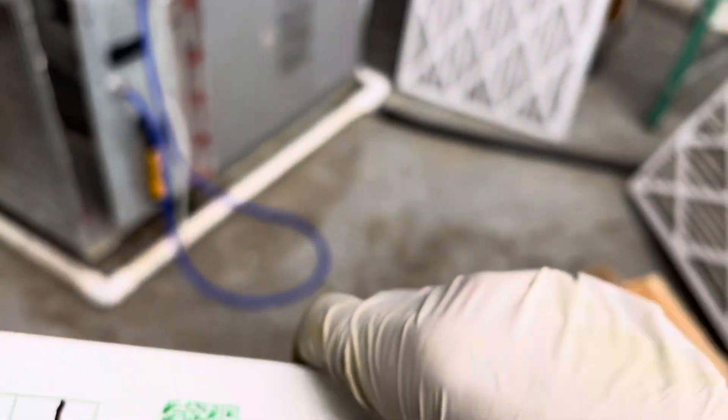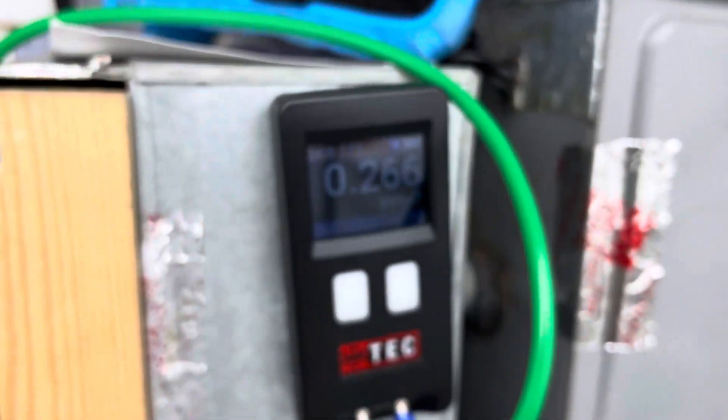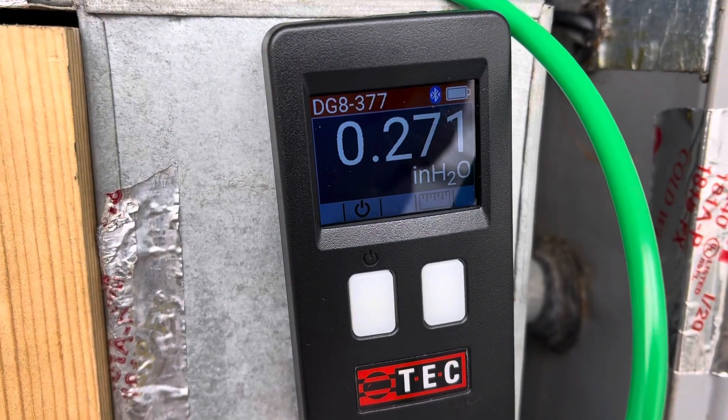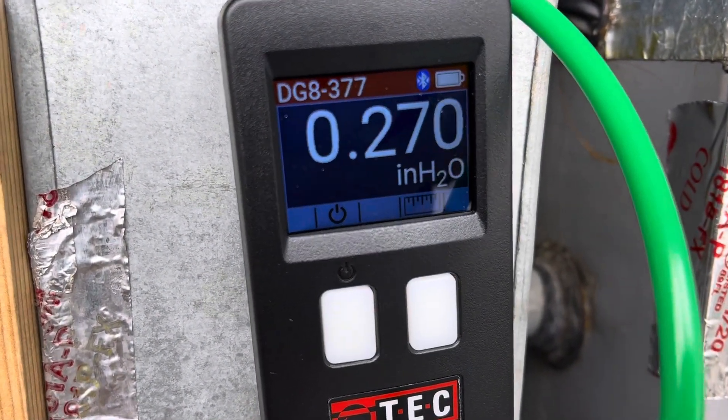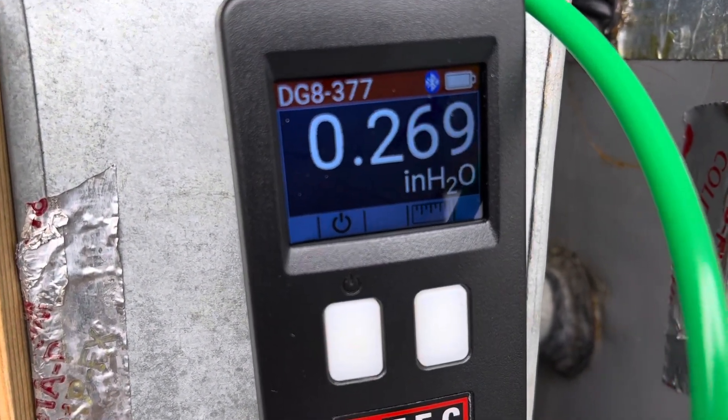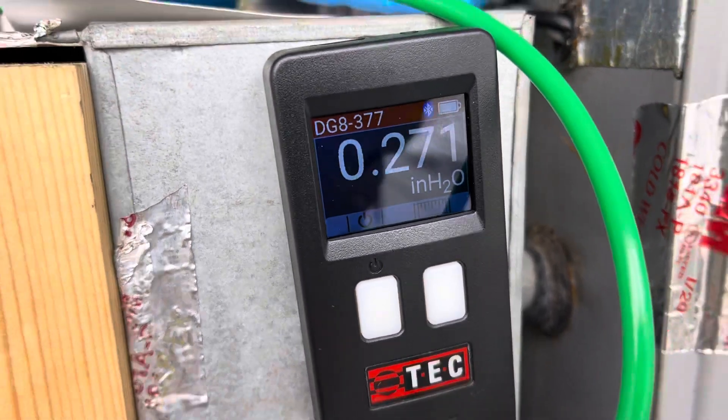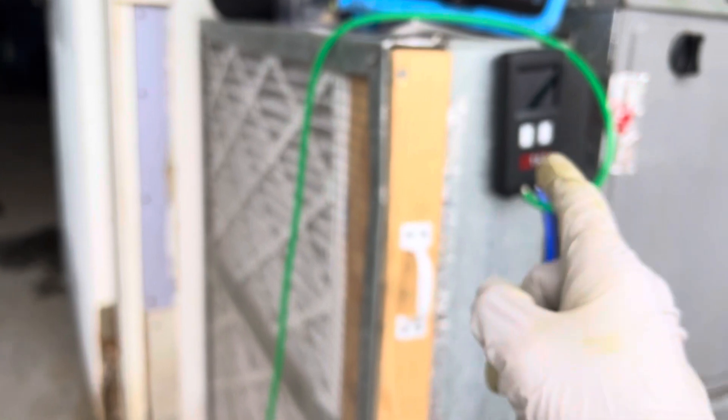Now we'll put the clean filters in. We were at 288 to 290, that was our steady rate. And now we're at a steady 270 right there, just by changing the filters.